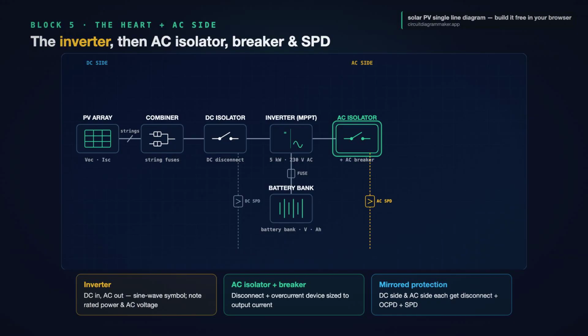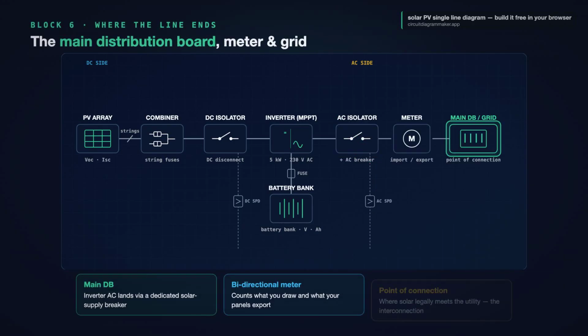Block 6, the main distribution board, the meter, and the grid connection. The inverter's AC output lands in your main distribution board, the consumer unit, usually through a dedicated breaker labeled as the solar supply. From there, the system ties to the utility, and in the middle sits the meter. On a grid-tied system, that meter runs both ways. It counts what you draw from the grid and what your panels export back to it. On the single line diagram, you show the point of connection clearly, where your solar system legally meets the utility, because that boundary is exactly what the interconnection approval is about. Board, meter, grid. That is where the line ends.